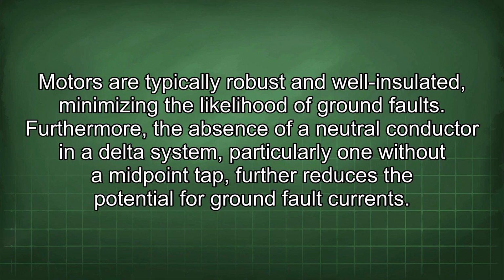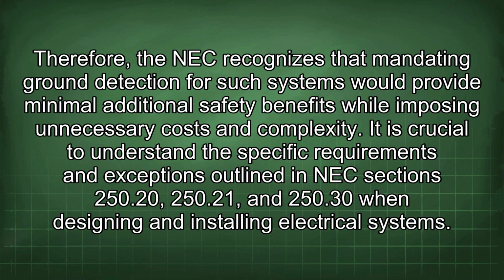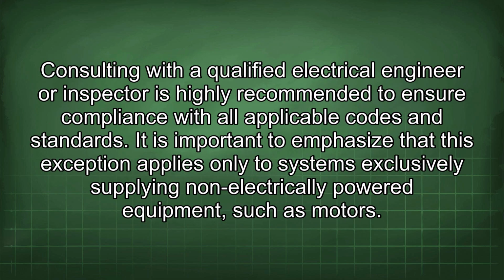Furthermore, the absence of a neutral conductor in a delta system, particularly one without a midpoint tap, further reduces the potential for ground fault currents. Therefore, the NEC recognizes that mandating ground detection for such systems would provide minimal additional safety benefits while imposing unnecessary costs and complexity. It is crucial to understand the specific requirements and exceptions outlined in NEC sections 250.20, 250.21, and 250.30 when designing and installing electrical systems. Consulting with a qualified electrical engineer or inspector is highly recommended to ensure compliance with all applicable codes and standards.